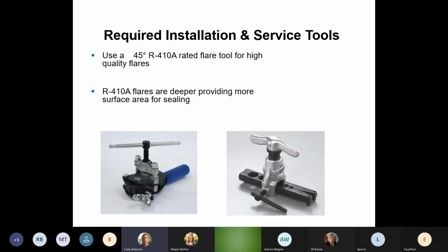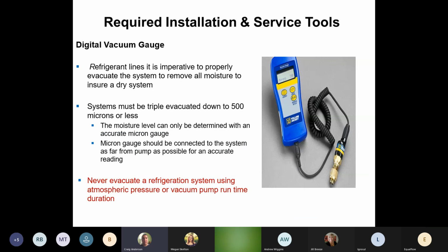Digital vacuum gauge. If you guys do not have one of these in your truck, you need to get one of these in your truck. This is the only way to properly check to see if you have a proper vacuum. We need to pull it under 500 microns. Looking at your gauge, timing it for 15 or 20 minutes is not going to tell you if you have the proper vacuum on that unit. So digital vacuum gauge, if you don't have one, you need to get one, whether you're installing or doing service. If you're doing service, chances are you're going to be pulling a vacuum at some point on an air conditioning system. You need a digital vacuum gauge.